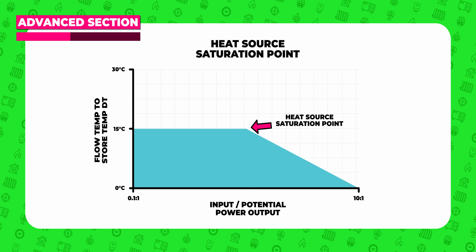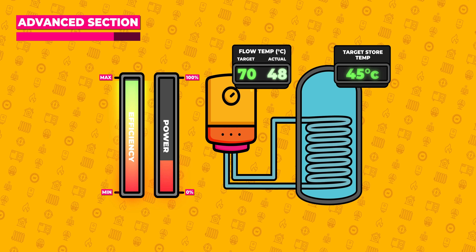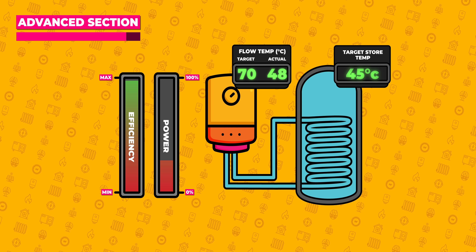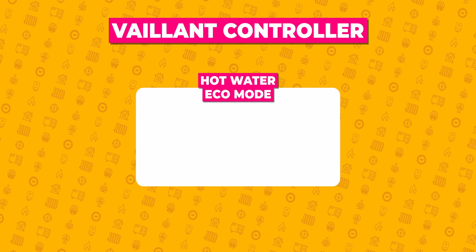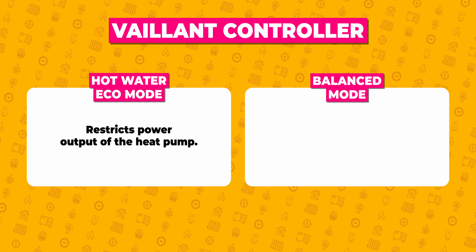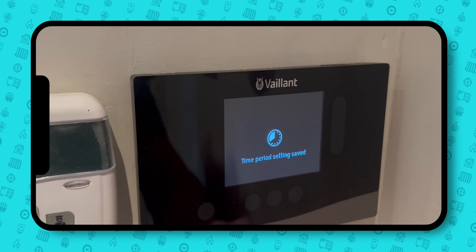We can effectively go even further past the heat source saturation point by changing some settings. Because this is to do with the ratio of power available at the heat source versus the potential power available at the cylinder's heat exchanger, if we restrict the heat pump or boiler's power output, the distortion will have to shrink as the heat source is even further outstripped of energy — giving us even lower flow temperatures and even higher efficiencies. To lower the heat output of a boiler, look for a range rating setting in the manual. For heat pumps there's less likely to be a range rating setting, but there are other settings that basically do the same thing. Vaillant has a hot water eco mode which restricts the power output of the heat pump during hot water, or balanced mode which restricts it until a certain temperature to gain efficiency. The other option to reduce power output on a Vaillant is the noise reduction mode — you can use this timer to reduce the heat pump output by between 35 and 60 percent during your hot water heat-up periods.